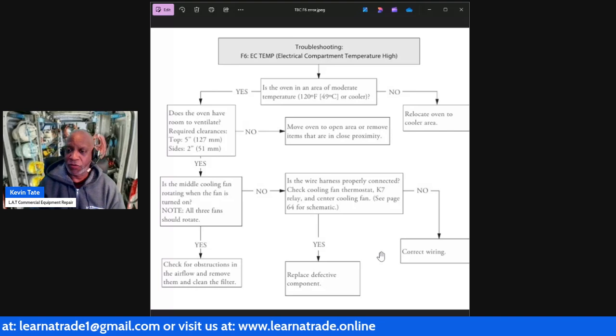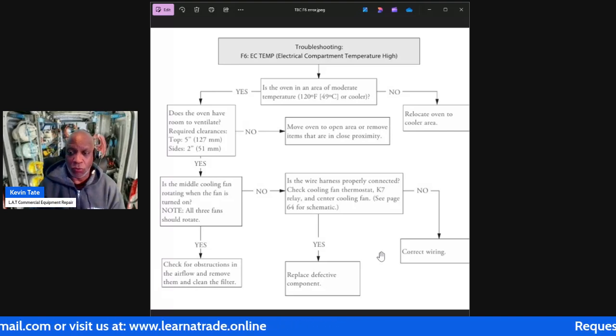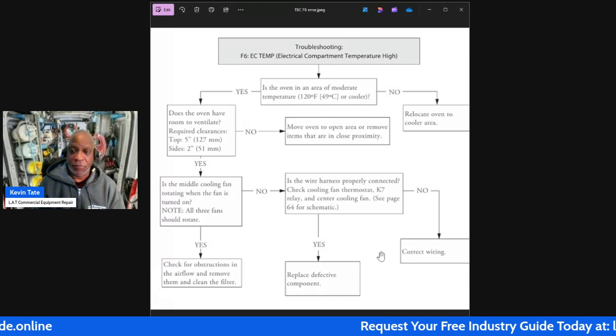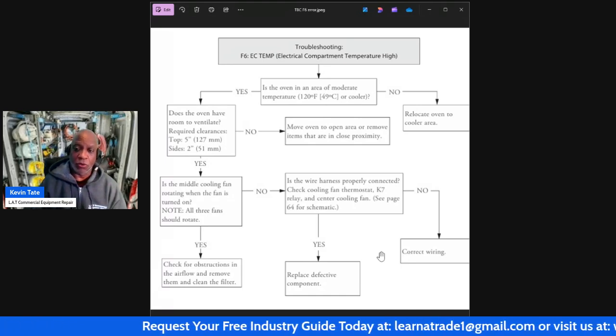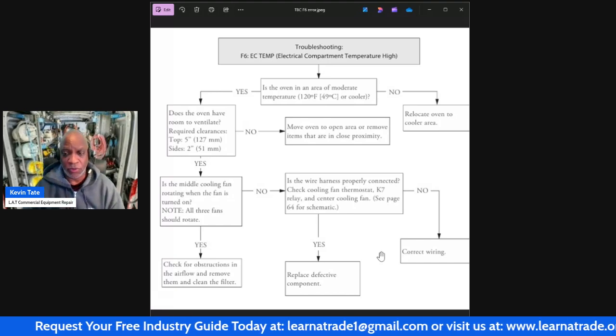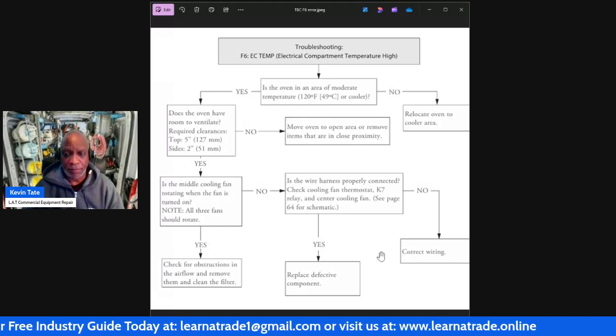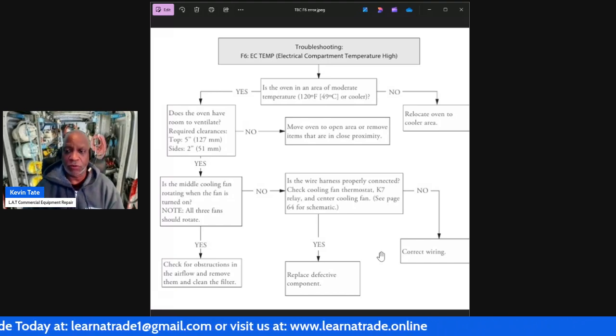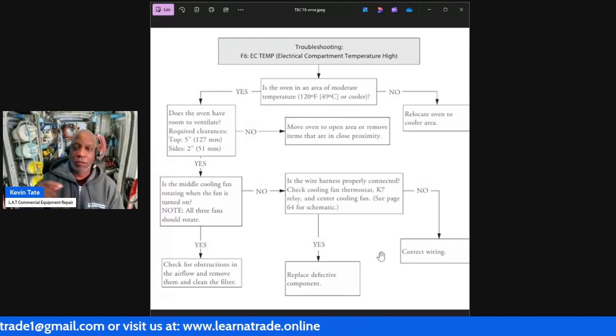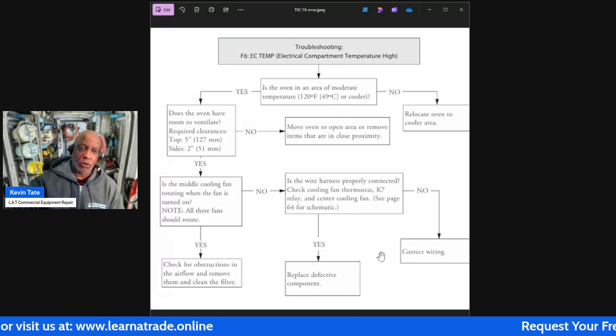Then it says check the cooling fan thermostat, the K7 relay, and the center cooling fan. When you trace that wiring, you'll see it feeds over to the K7 relay.